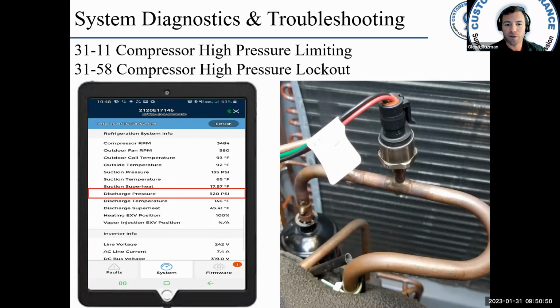3111 and 3158. This is compressor high pressure limiting and compressor high pressure lockout. So the high pressure limit is based on the compressor model and varies with operating speed. Okay, when this fault occurs, the system will shut down and restart after a 5-minute delay if demand is still present. Each time the fault occurs, the maximum allowable compressor speed will be reduced by 25% until the minimum is reached.